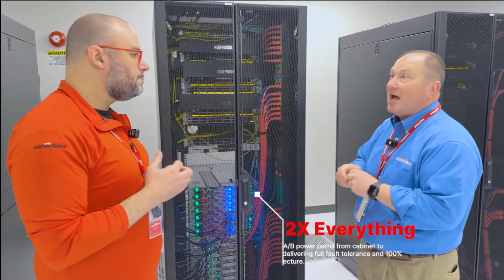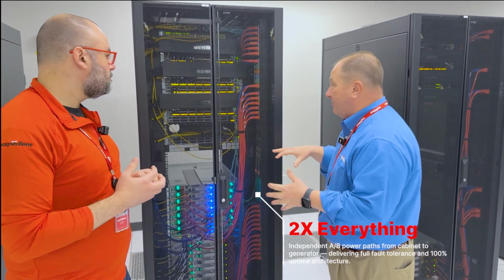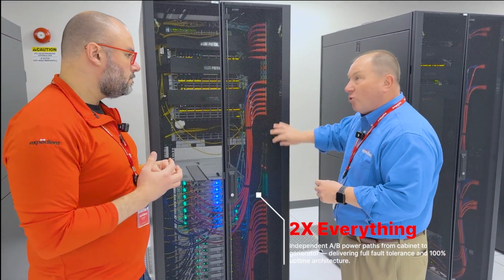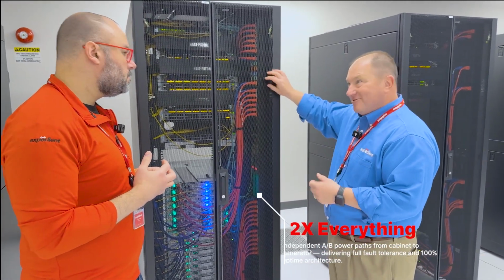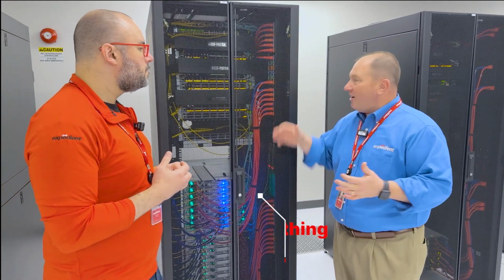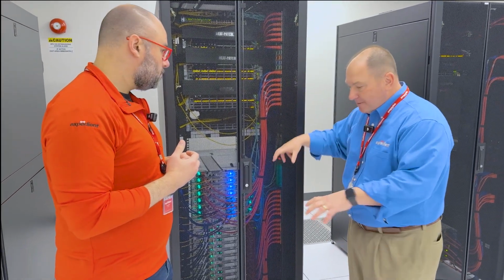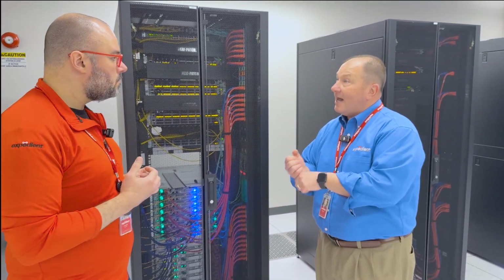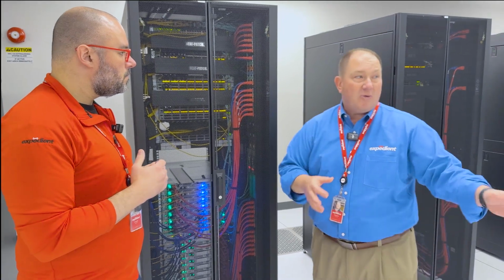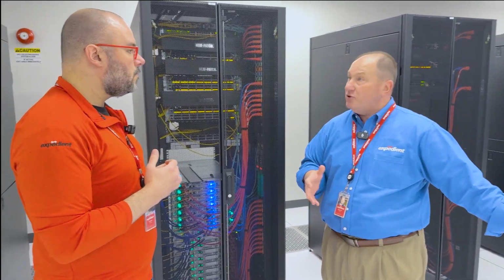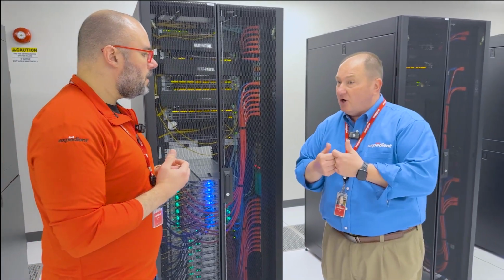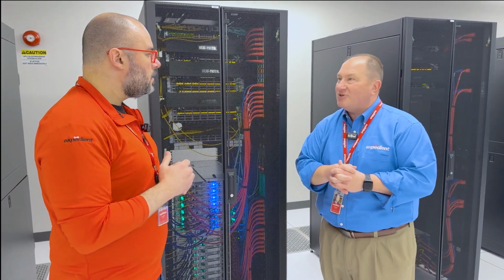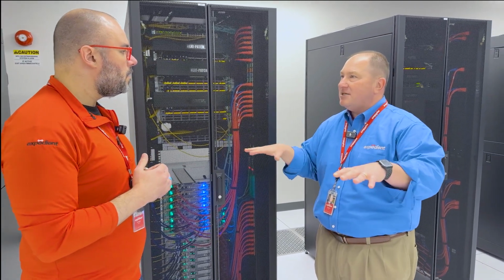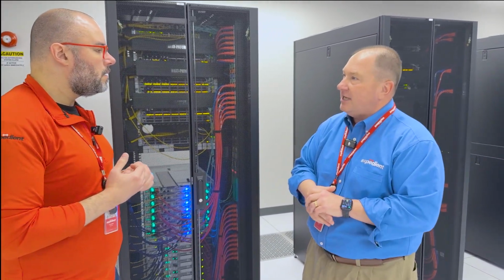So that means it's 2 times our need. We have an A and a B feed - the A is our red cord and the B is our blue cord. We carry that all the way through the cabinets, the PDUs, and the conduit under the floor that houses the electrical connections, all the way back to our power distribution units, which are labeled and color-coded red and blue. You'll even see later on the tour that we carry that through the UPS and the power room scheme so we can clearly delineate it.